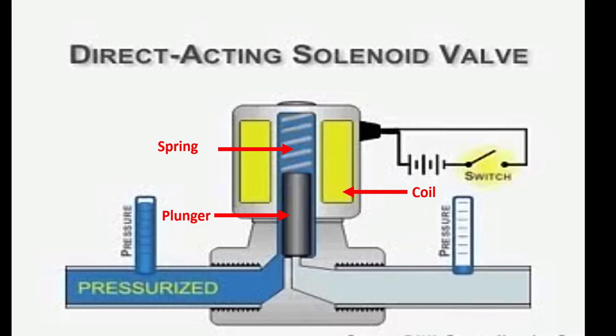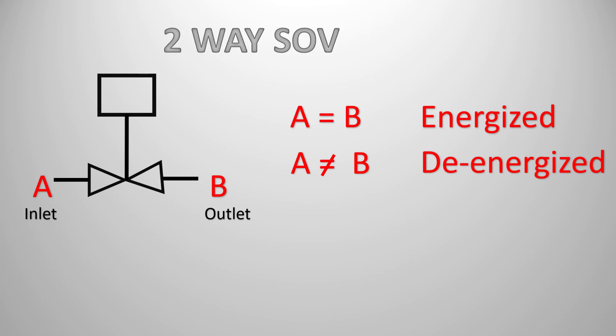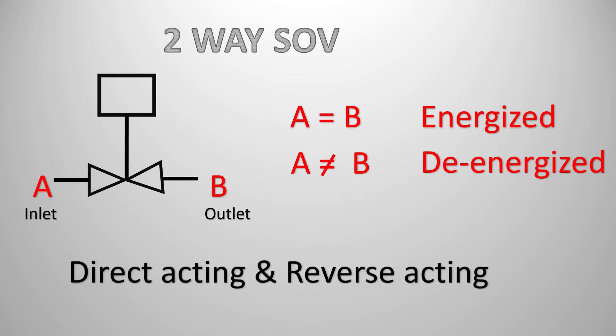There are different types of solenoid valves. A two-way solenoid valve has two ports: port A is the inlet and port B is the outlet. When the solenoid valve gets energized, A equals B, meaning the inlet and outlet ports get connected. When the solenoid coil de-energizes, A is not equal to B, so both ports get disconnected. We also have direct-acting and reverse-acting solenoid valves, which work vice versa.